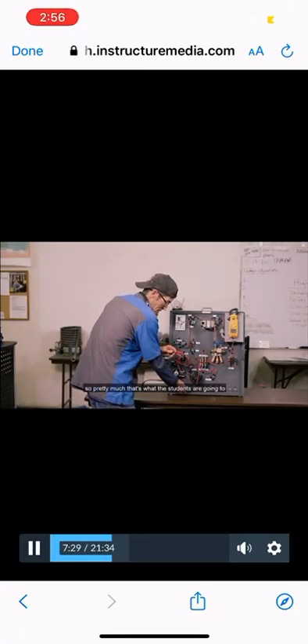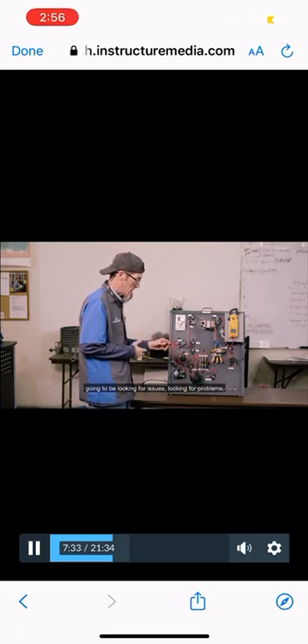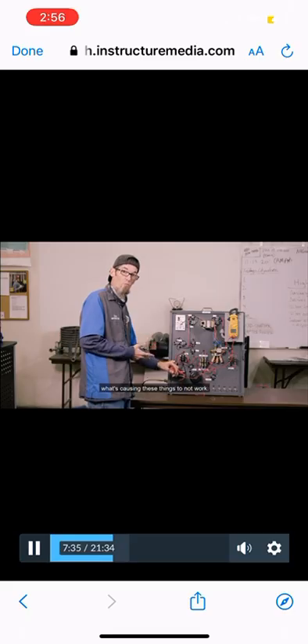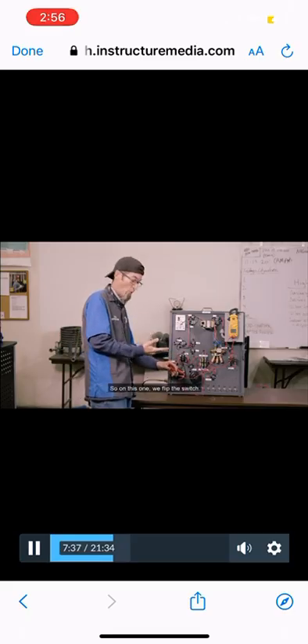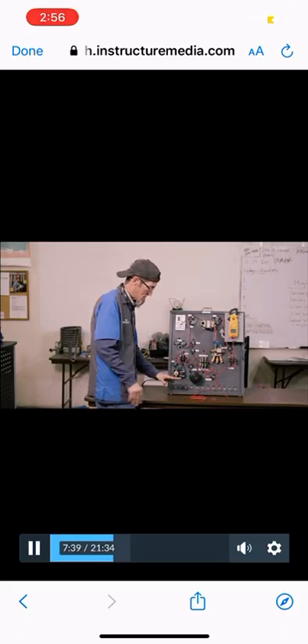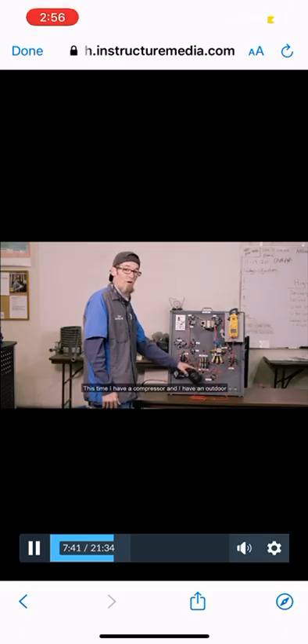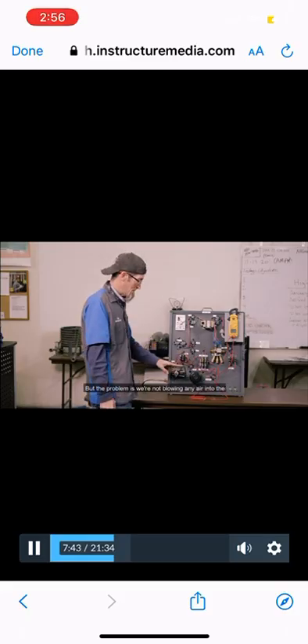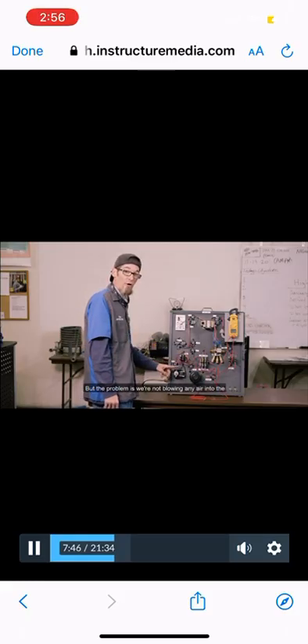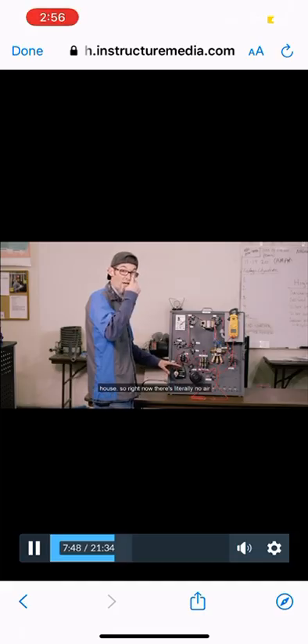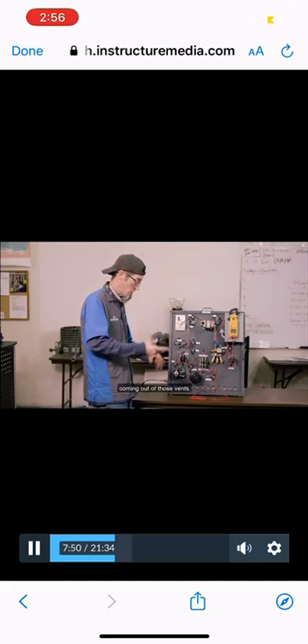Okay, so pretty much that's what the students are going to be doing on this electronic troubleshooting, is they're going to be looking for issues, looking for problems. What's causing these things to not work? So on this one, we flipped the switch. This time, I have a compressor and I have an outdoor fan, which is a good sign. But the problem is we're not blowing any air into the house. Okay, so right now there's literally no air coming out of those vents.